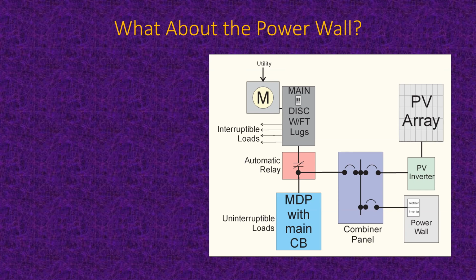It's pretty common down in my neighborhood for that main up on top to be a 150 amp breaker and a 200 amp panel, and the bottom one, the blue one, to be a 200 amp panel, and no additional circuit breakers there.